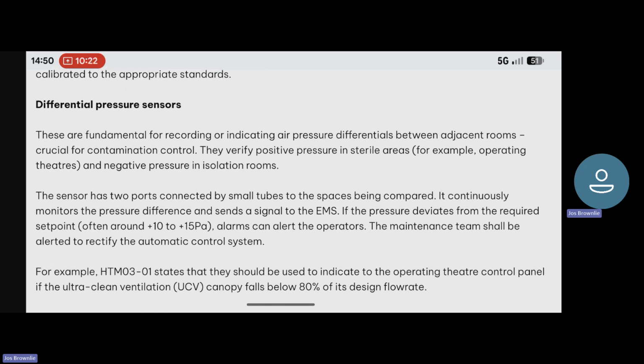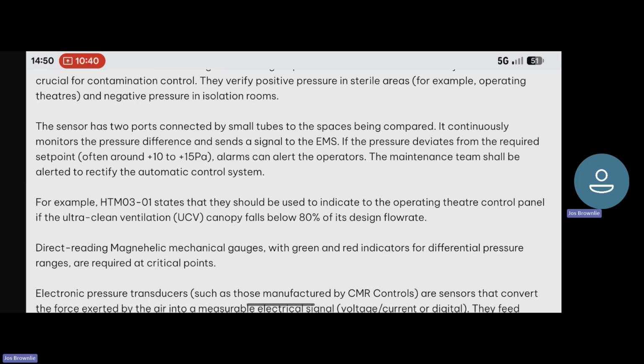Differential pressure sensors. These are fundamental for recording or indicating air pressure differentials between adjacent rooms, crucial for contamination control. They verify positive pressure in sterile areas, for example operating theatres, and negative pressure in isolation rooms. The sensor has two ports connected by small tubes to the spaces being compared. It continuously monitors the pressure differential and sends a signal to the EMS.